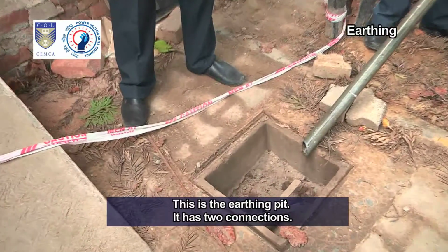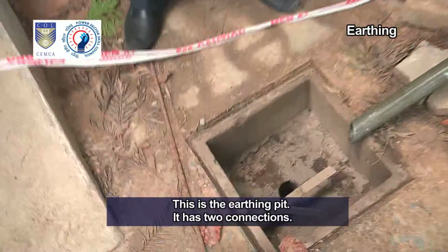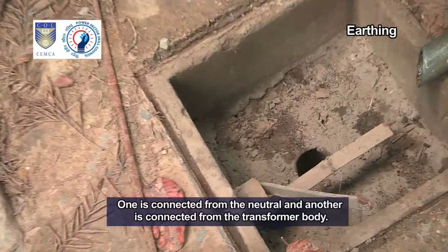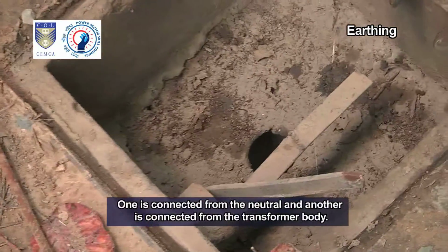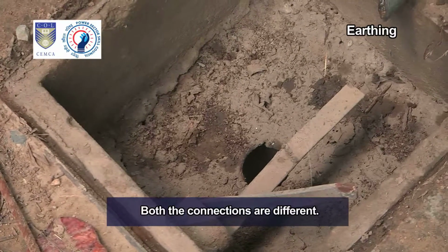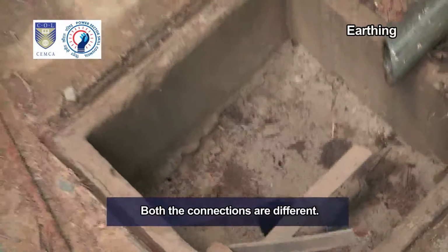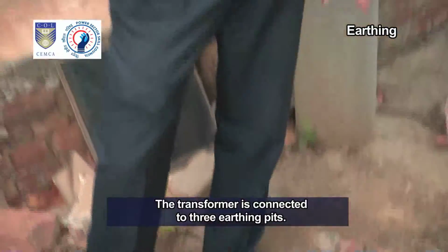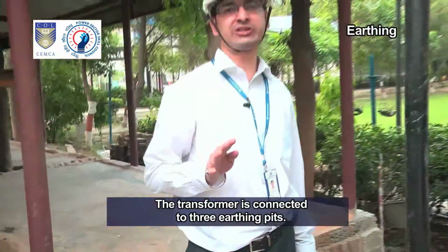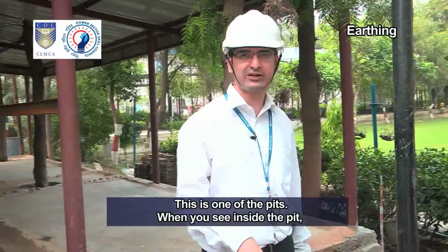This is the earthing pit. It has two connections. One is connected from the neutral and another is connected from the transformer body. Both the connections are different. The transformer is connected to 3 earthing pits. This is one of the pits.